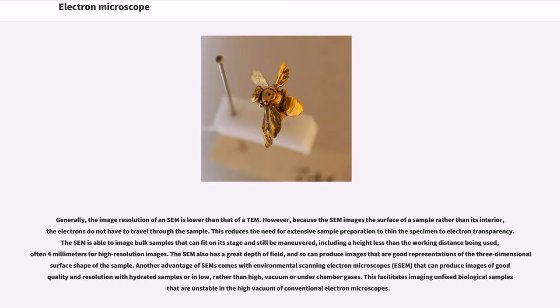This reduces the need for extensive sample preparation to thin the specimen to electron transparency. The SEM is able to image bulk samples that can fit on its stage and still be maneuvered, including a height less than the working distance being used, often 4 mm for high-resolution images.